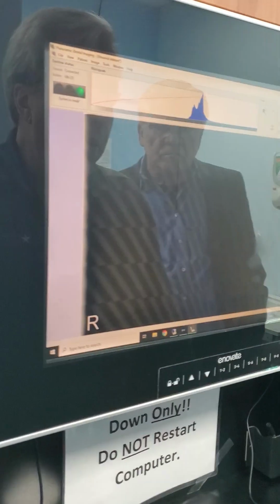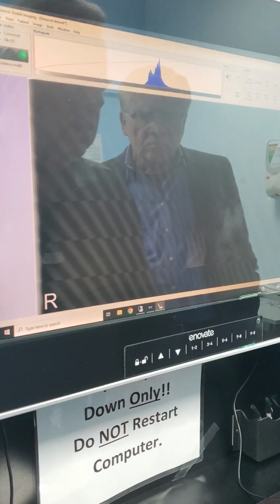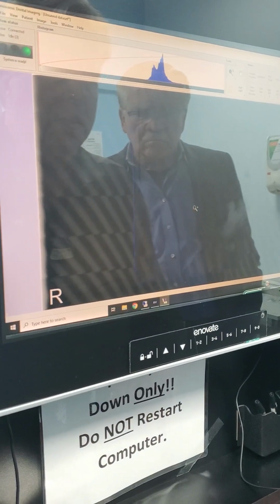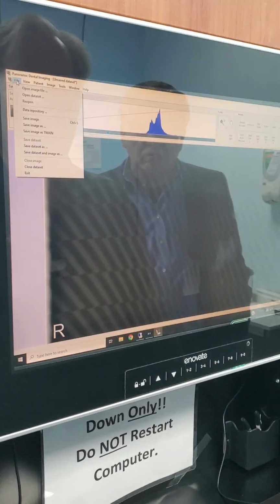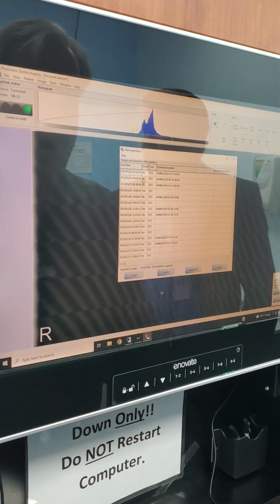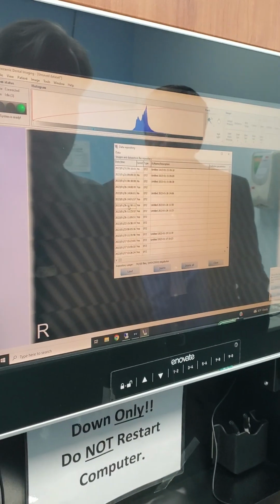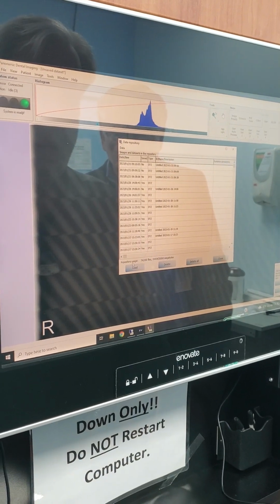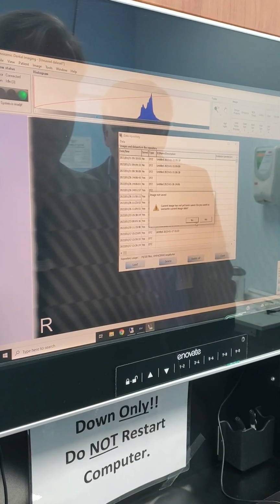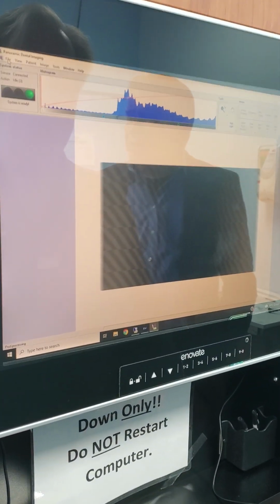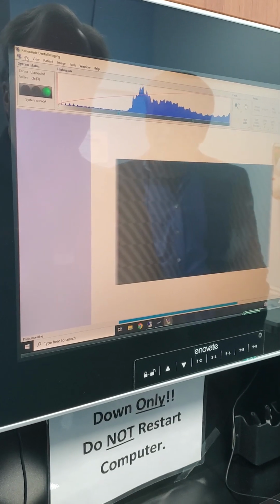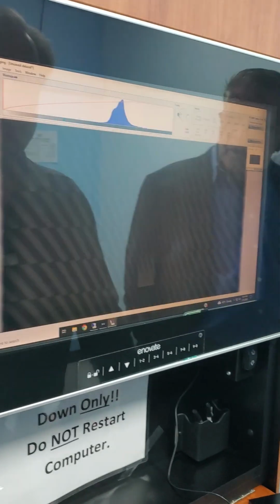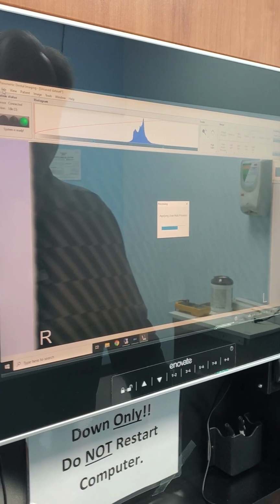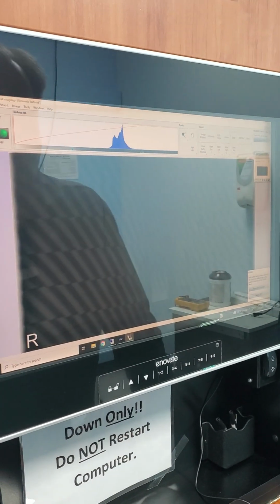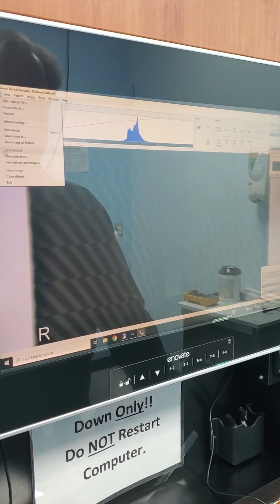So I said they look like grid lines almost. Are they all the way across the image? Yes. Let me see if I can see it on a. They're also looking a little blurry too, don't they? They kind of blur the image. And Panoramic said that's just a calibration issue, right? Yeah, it just needs to be calibrated. That's what they said, to get rid of those lines. Could the high KV be contributing to that, or just the out of calibration, the speed, a little combination of everything? I think it's mostly the calibration. Okay.